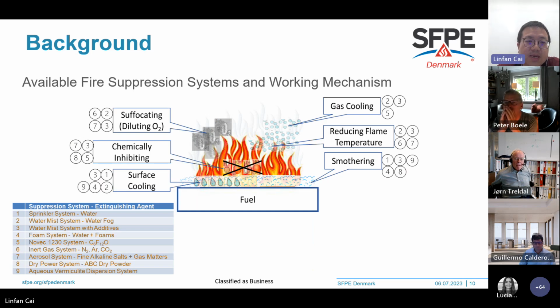So for this, I listed some of the common fire suppression systems that have been tested or experimented on lithium-ion battery fires. This consists of basically 1 to 9: the sprinkler system, water mist with and without additive, foam system, novec inert gases, aerosol system, dry powder, and AVD. AVD is a special extinction media that actually covers a battery when it melts.